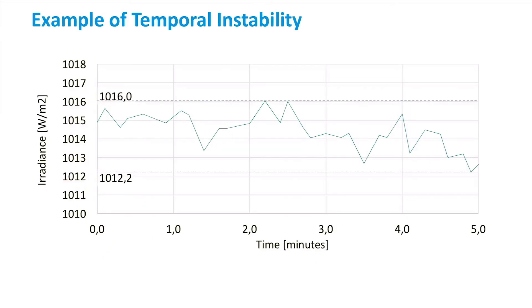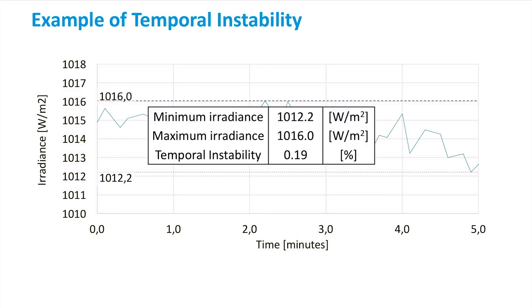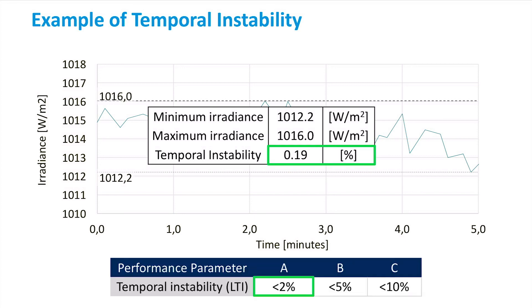The irradiance measurements are carried out in the simulator via a current-voltage measurement system which consists of a suitable test cell connected to a source meter unit. The short-circuit current of the cell is measured repeatedly over the required time period, as shown in the graph, where the typical irradiance of the steady-state simulator is plotted as a function of time, highlighting its fluctuations. By using the maximum and minimum irradiance measured, it is possible to obtain the temporal instability, also called irradiance deviation. In this example, the solar simulator scored an A because the instability is lower than 2%.